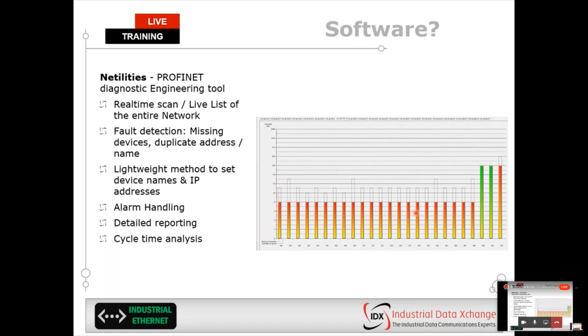Over here you can see there's a whole lot of devices connected, and all these devices that are red are suffering from jitter. It's not very clear here, but it's supposed to be communicating 8 milliseconds, but at some point it's taken close to 32 milliseconds, or in some cases close to 64 milliseconds to communicate. So quite a huge amount of jitter here, and it's important to identify if there's jitter on my network and make a mitigating step based on that.